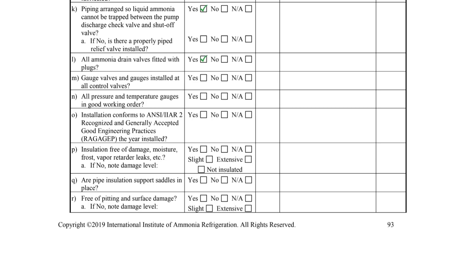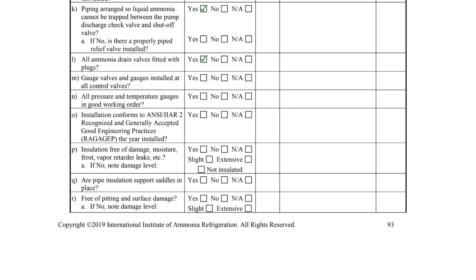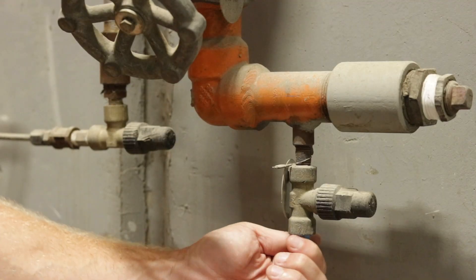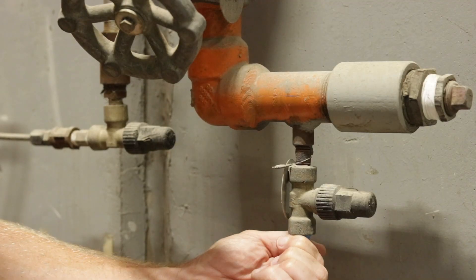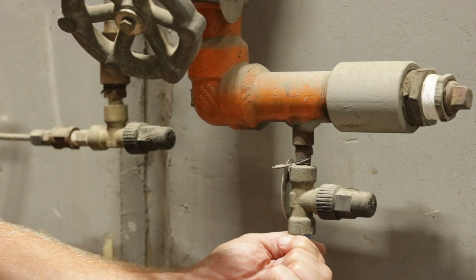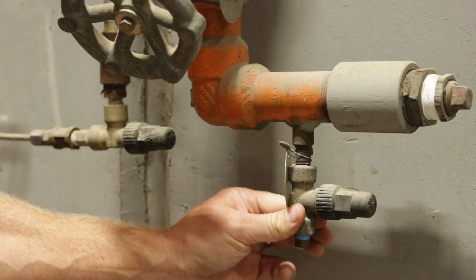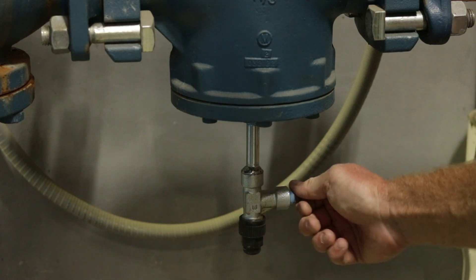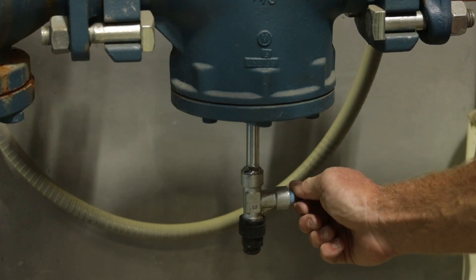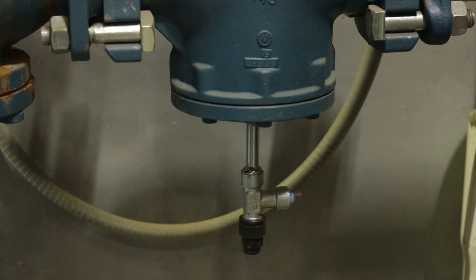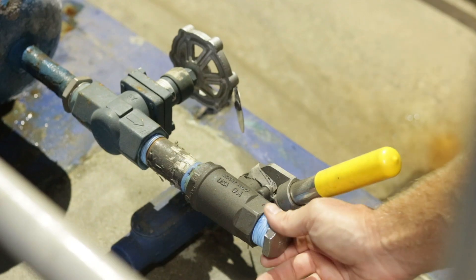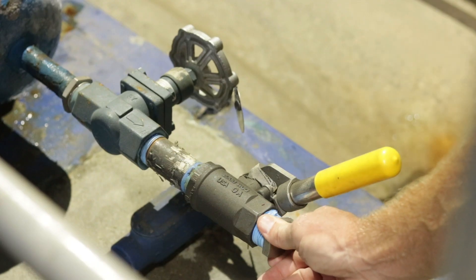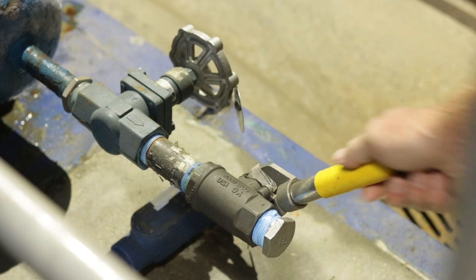Item L asks if all the ammonia drain valves are fitted with plugs. It is imperative that all valves connecting the ammonia refrigeration system to the atmosphere be capped, plugged, blanked, or locked closed when they are not in use.